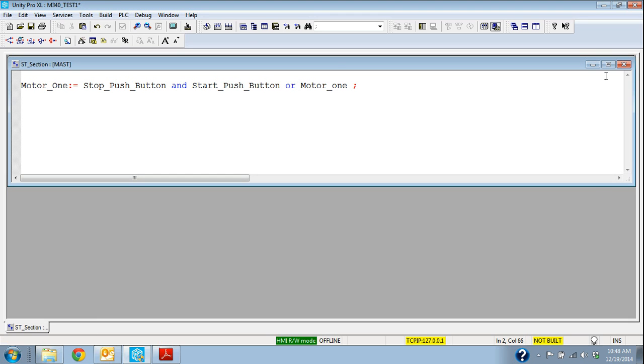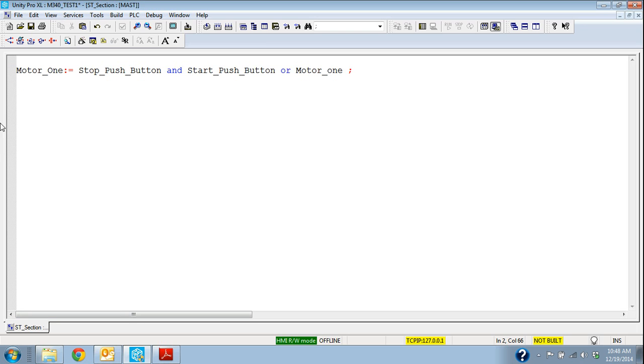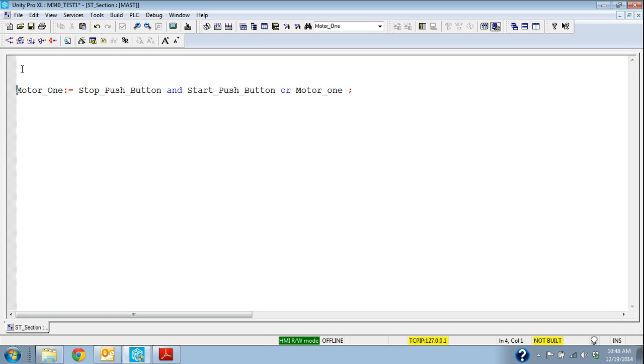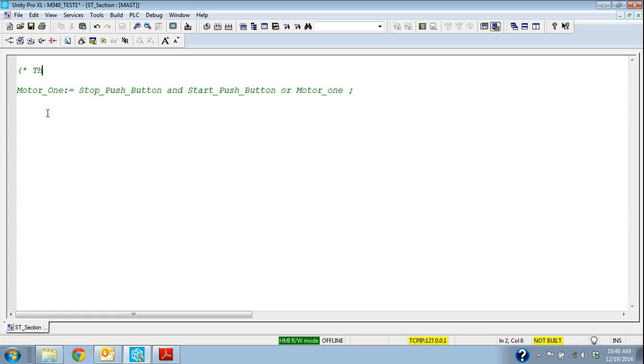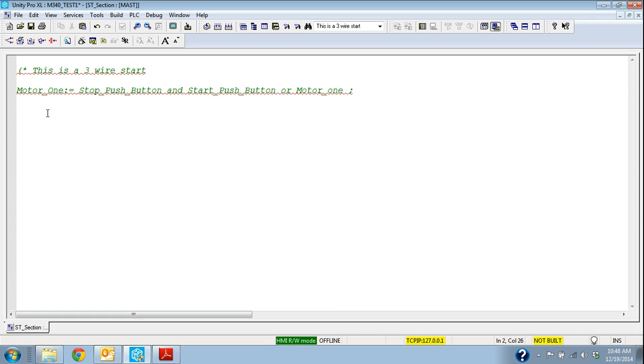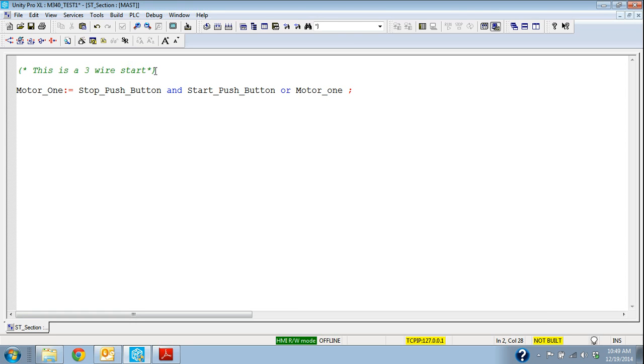The other thing I wanted to show you that's kind of handy with structured text is I can add notes in here. So if I put a bracket and a star and I can say this is three wire start and then I can close with a star and a bracket. So as long as I have a star in a bracket at the beginning and the end I can put all kinds of comments in here and it's not going to pick it up like logic. I can explain to people what I'm doing in the structured text section.